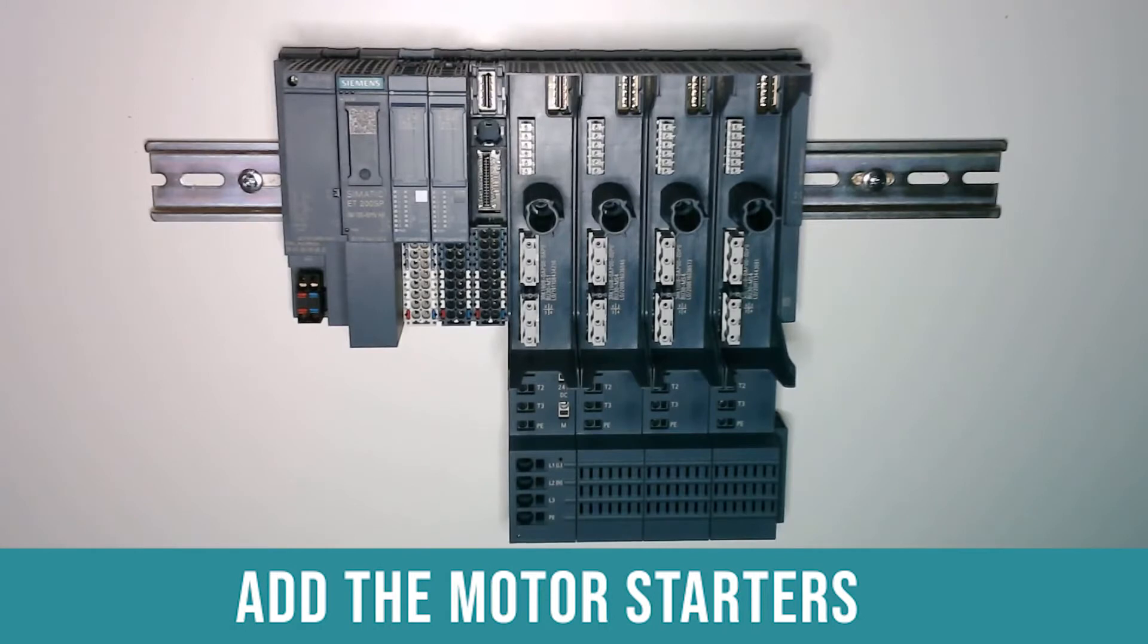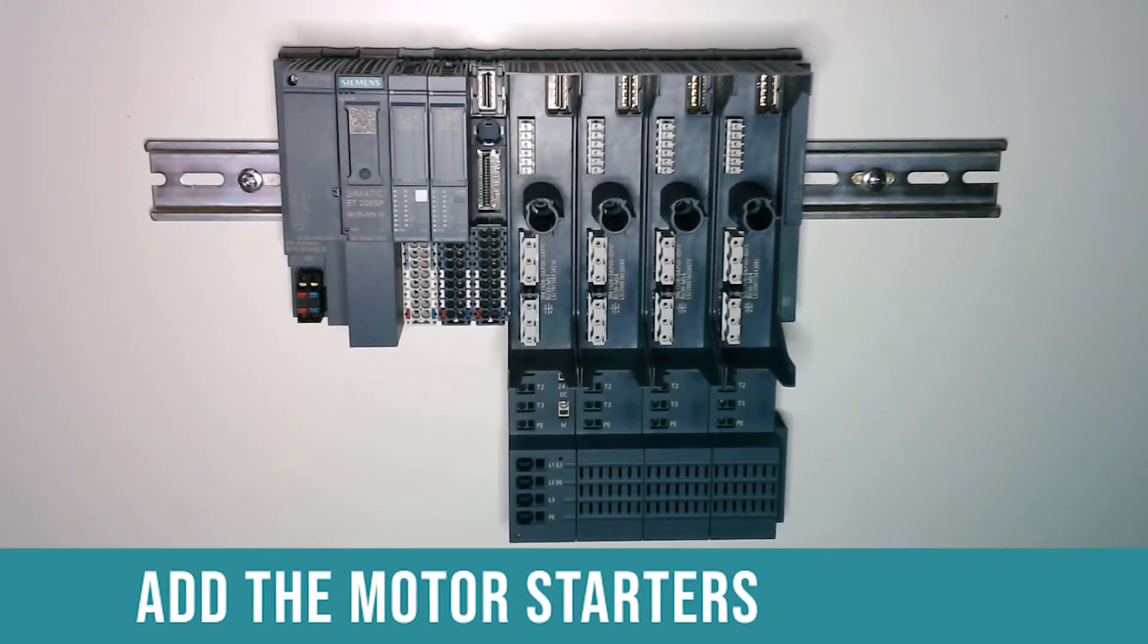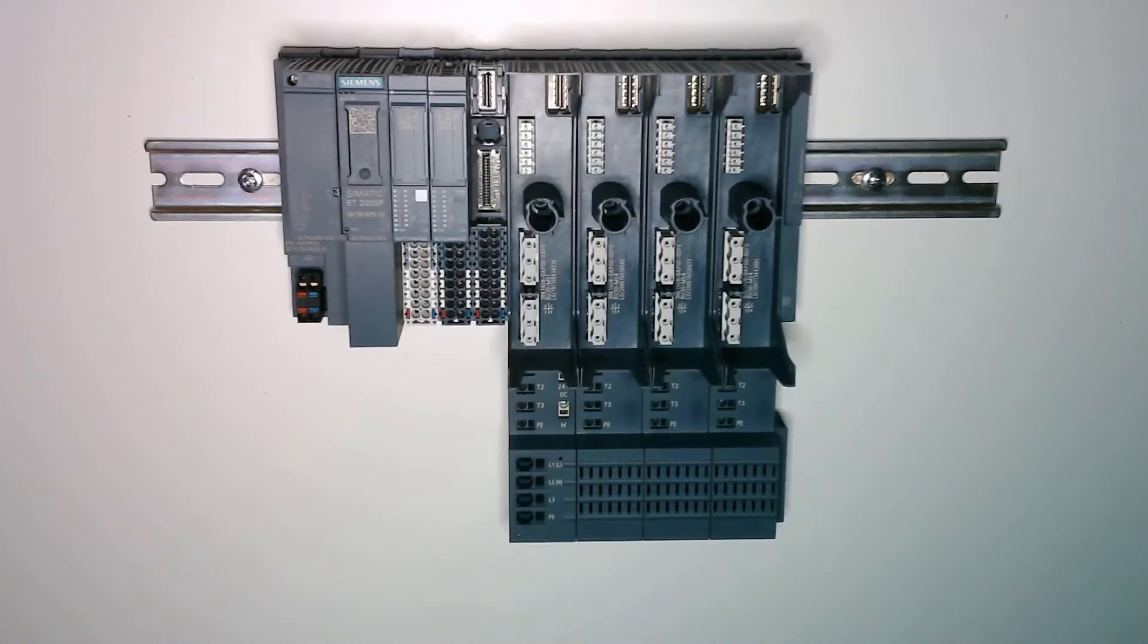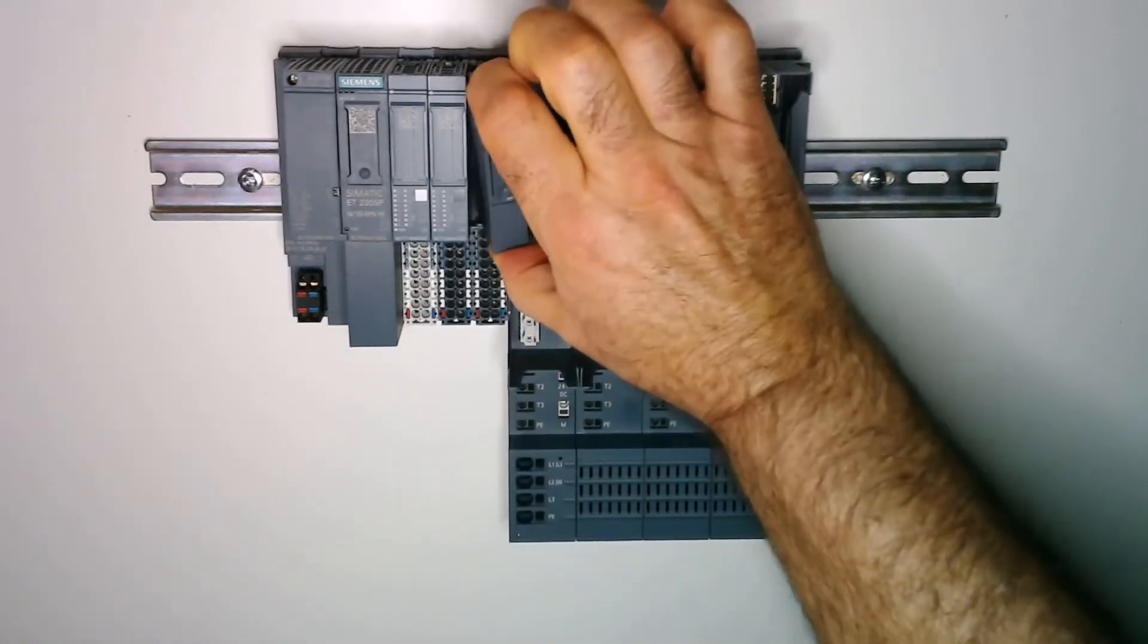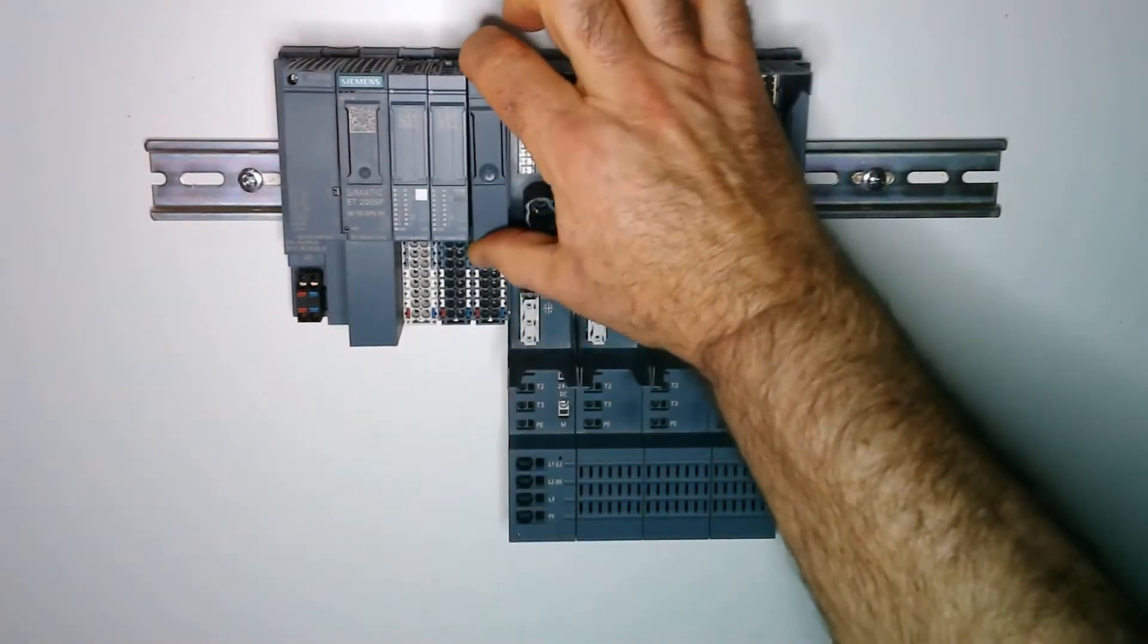When installing motor starters in ET200SP you need to put in one empty base for isolation. I will put a cover in to cover that.